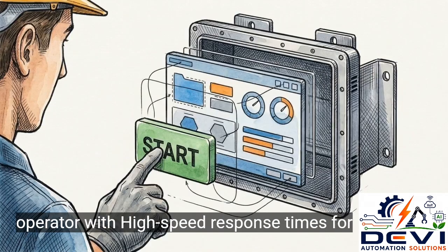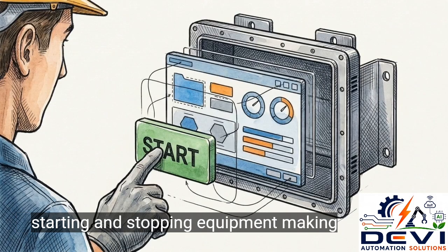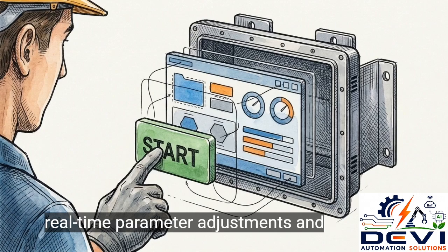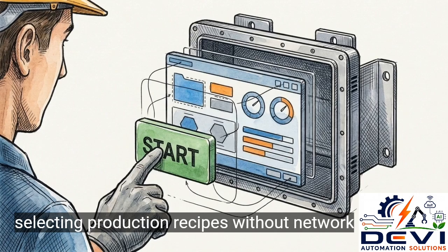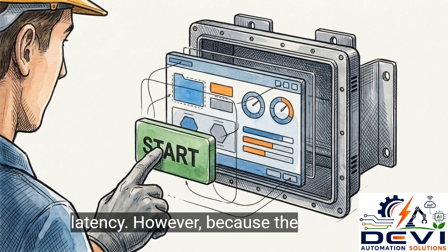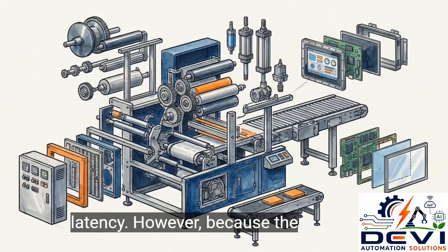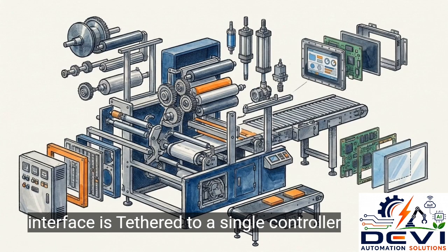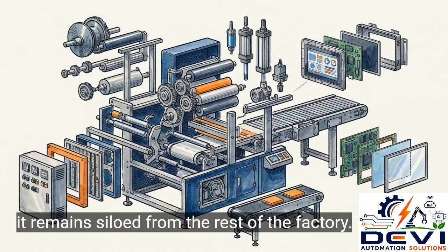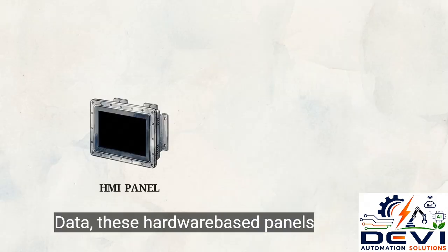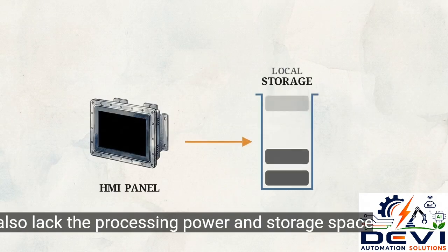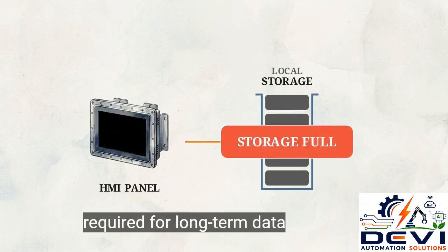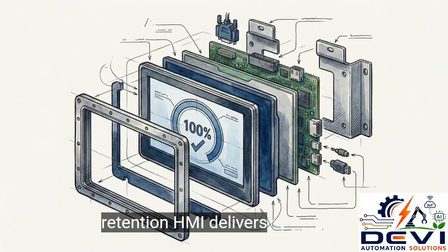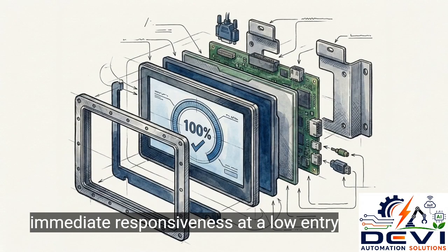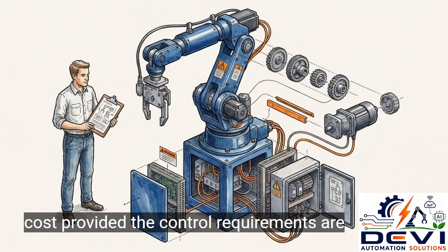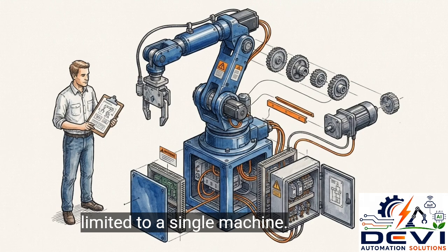This provides the operator with high-speed response times for starting and stopping equipment, making real-time parameter adjustments, and selecting production recipes without network latency. However, because the interface is tethered to a single controller, it remains siloed from the rest of the factory's data. These hardware-based panels also lack the processing power and storage space required for long-term data retention. HMI delivers immediate responsiveness at a low entry cost, provided the control requirements are limited to a single machine.